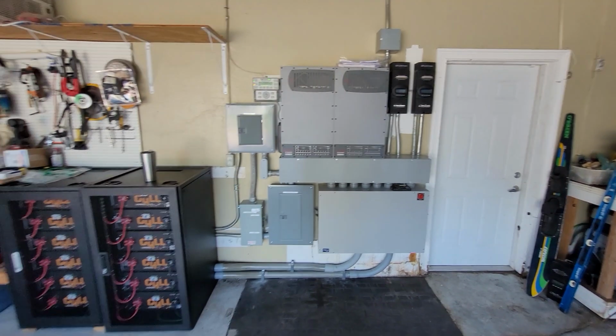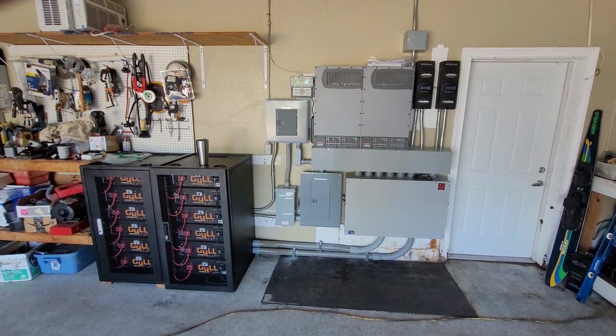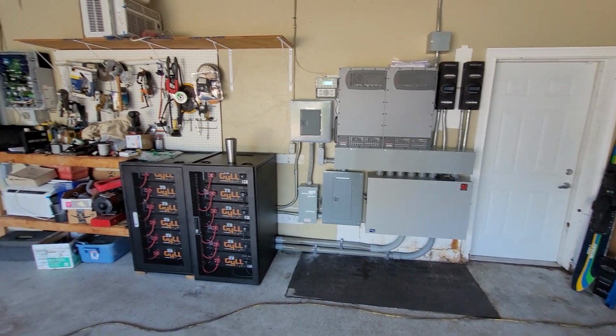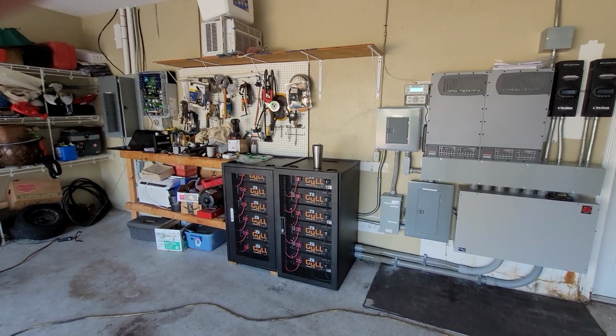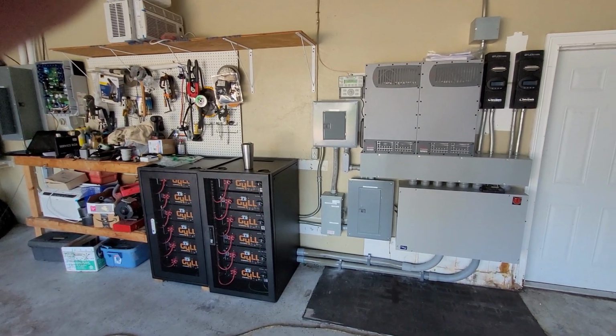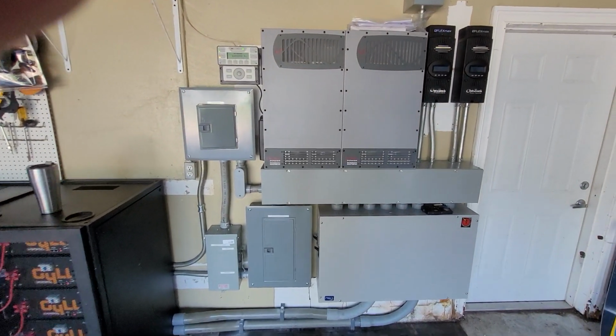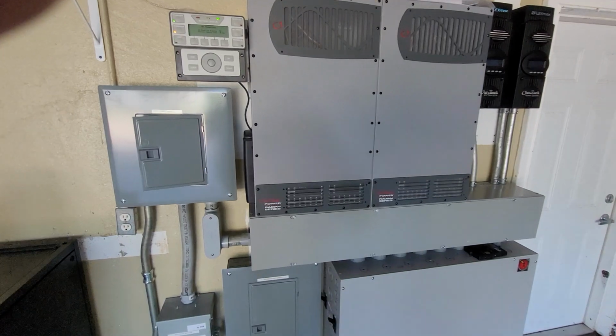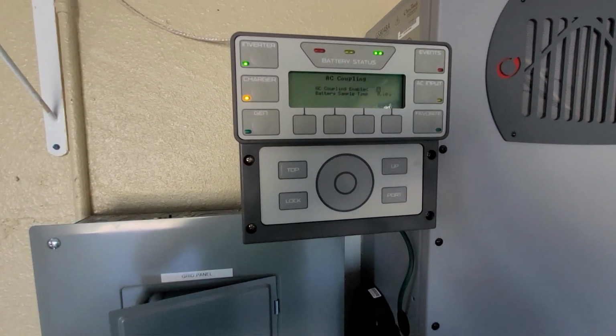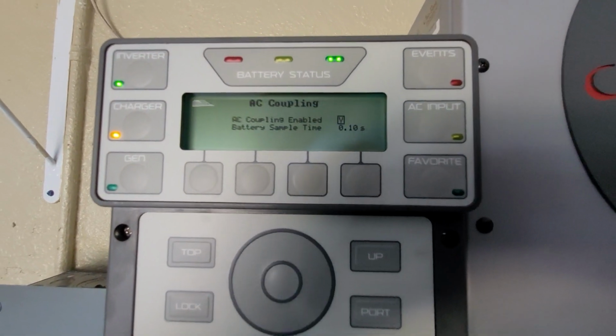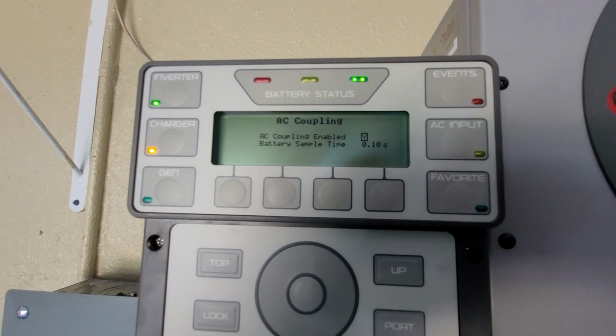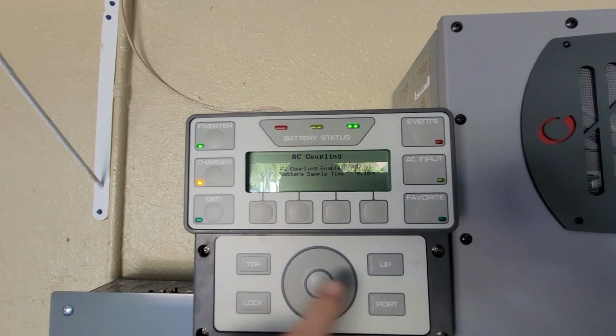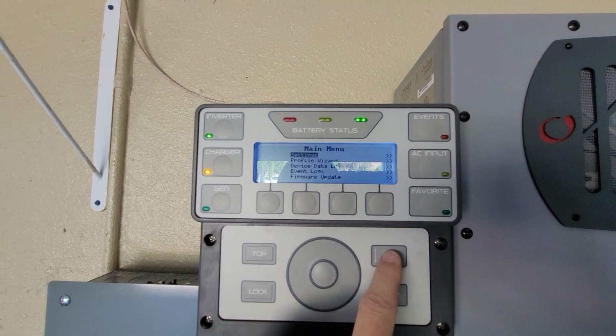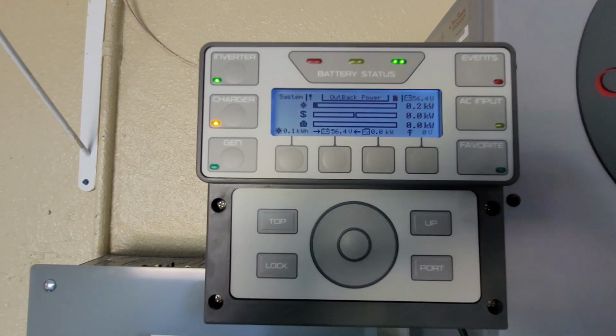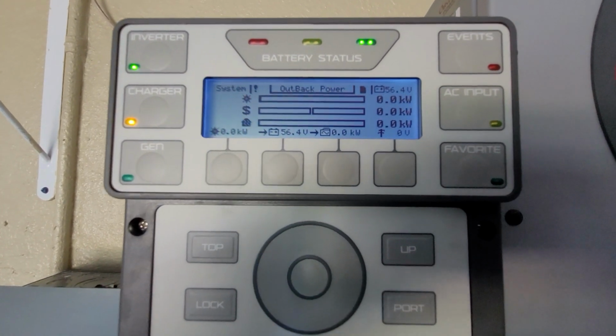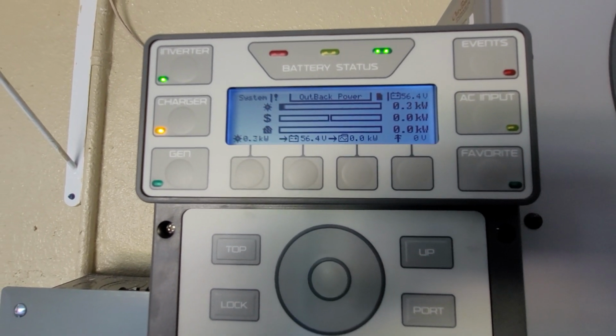So this is how to properly get a battery-based system to AC couple and kind of what it'll look like on the displays. So this is a dual Radian system, and here you can see the battery sampling time I've set. And you can see here that there's no load really showing up.